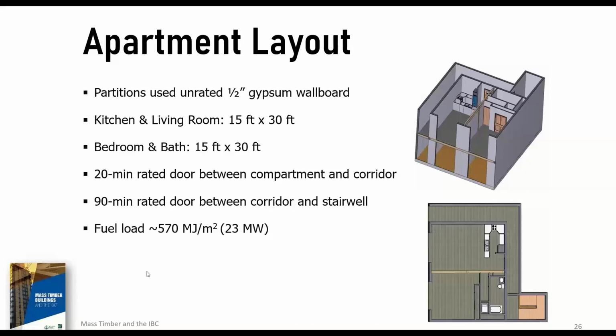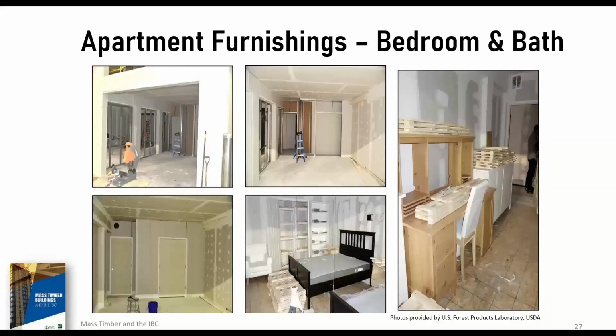So the apartment layout: we already talked about the demising wall with 1/2-inch gypsum between the living room and bedroom space. Each compartment is roughly 15 by 30. We talked about the 20-minute compartment door and the 90-minute rated door at the end of the corridor leading to the stairwell. And we talked about the fuel load. We'll talk about this 23 megawatts later in the presentation when we break down the individual tests. But the long and short of it was that the first test, where all the gypsum was covering the exposed mass timber elements, was 18 megawatts, and tests 2 and 3, which had some exposed mass timber elements, went up to 23 megawatts. So here is the typical configuration that was used throughout all 5 tests.